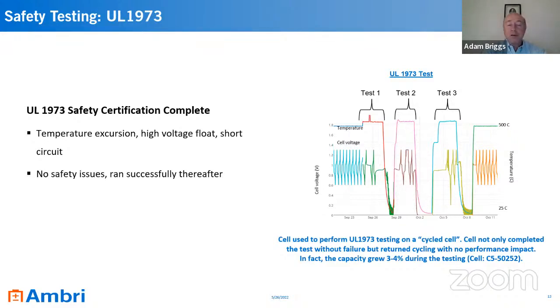In Ambri's case, we do not use or require any electronics around the cell, and none were used in this certification. They put it through the same type of tests: raise it to an elevated temperature, raise the cell to an elevated voltage, essentially overcharging, and then short circuit the cell. In all cases, pass or fail is whether there's a fire or explosion. In Ambri's case, none of those things occurred.